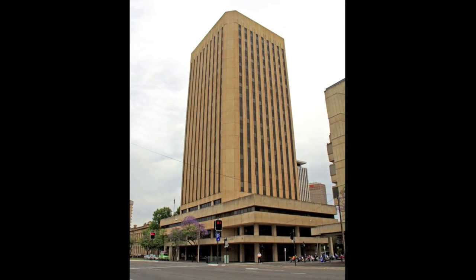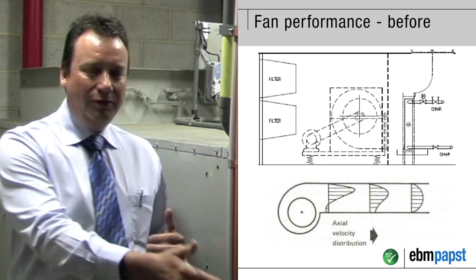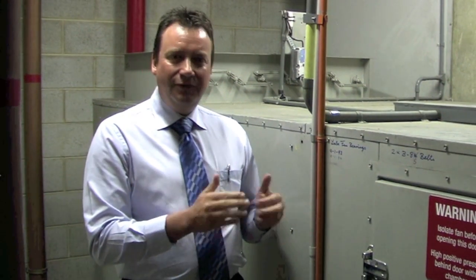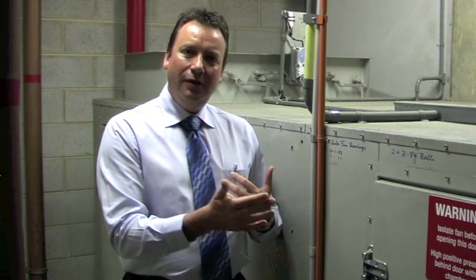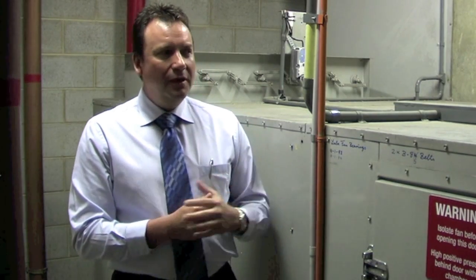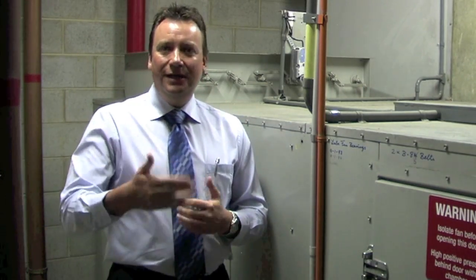Wakefield House is a 19-storey building. We were asked to be involved because the whole building suffers from a unique problem whereby the existing air handling unit contains a backward curved centrifugal fan, belt drive, whose mounting is so close to the cooling coil that the coil actually has very high velocity and a very non-laminar flow through the coil. Through modelling we were able to suggest and prove that we're probably losing about 20-25% cooling capacity because of the patching effect and the very high velocity. High velocity also imposed quite a high pressure drop, probably an order of 200 Pa more than the original designers expected, which resulted in a 10-15% reduction of airflow to the floor plate. This of course has an effect on both the air circulation, the outdoor air introduction, and the heating and cooling delivery to the floor itself.